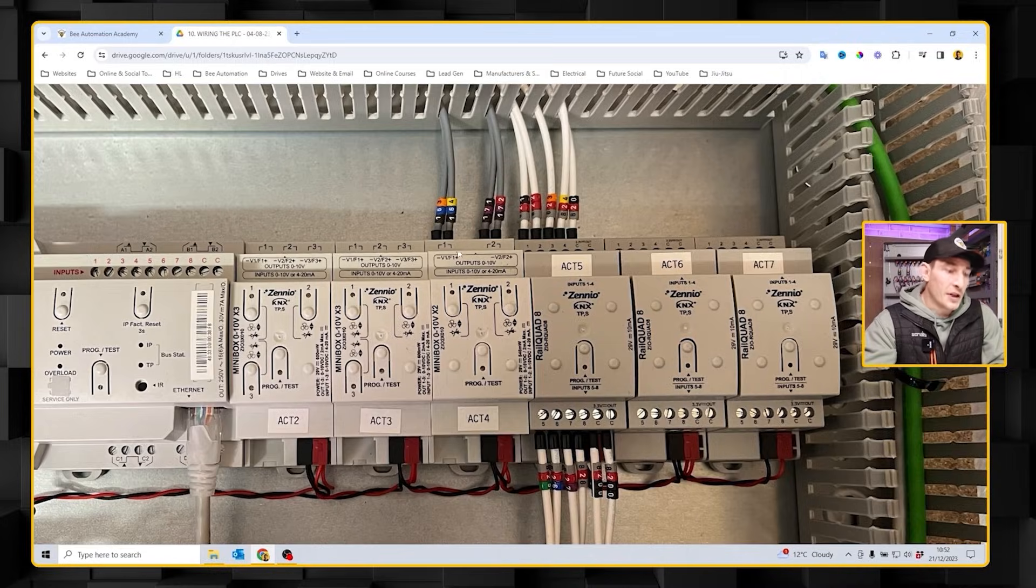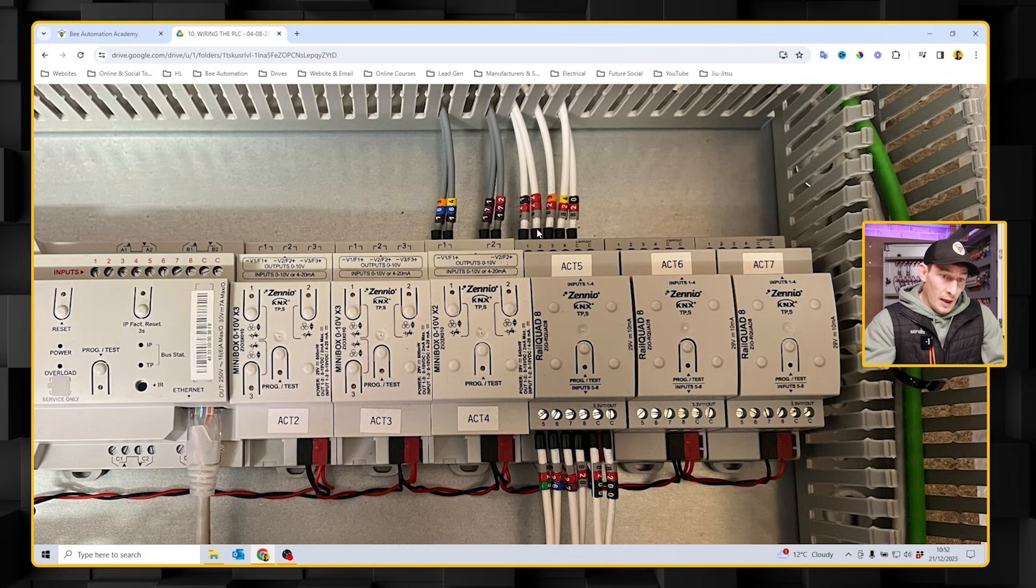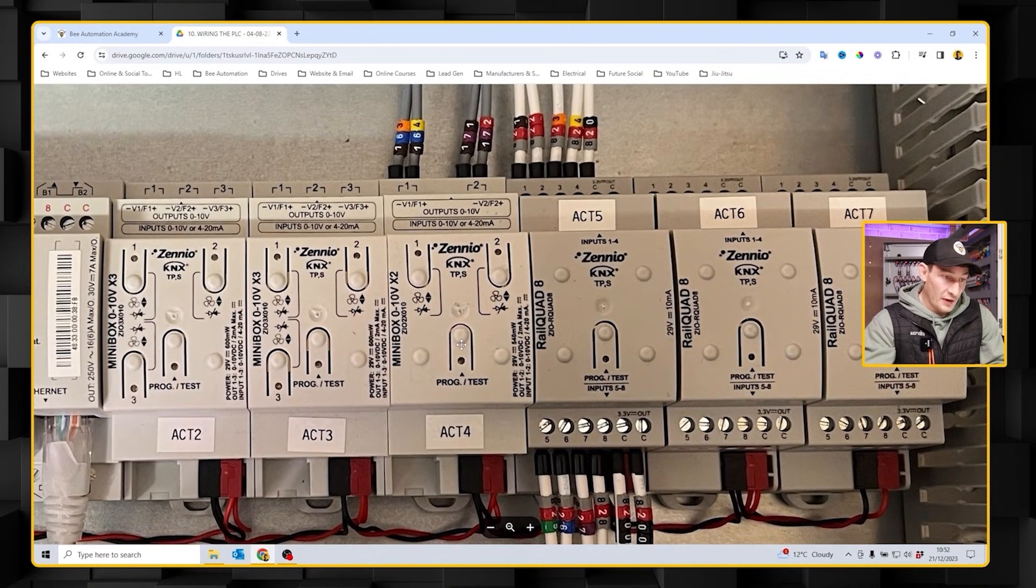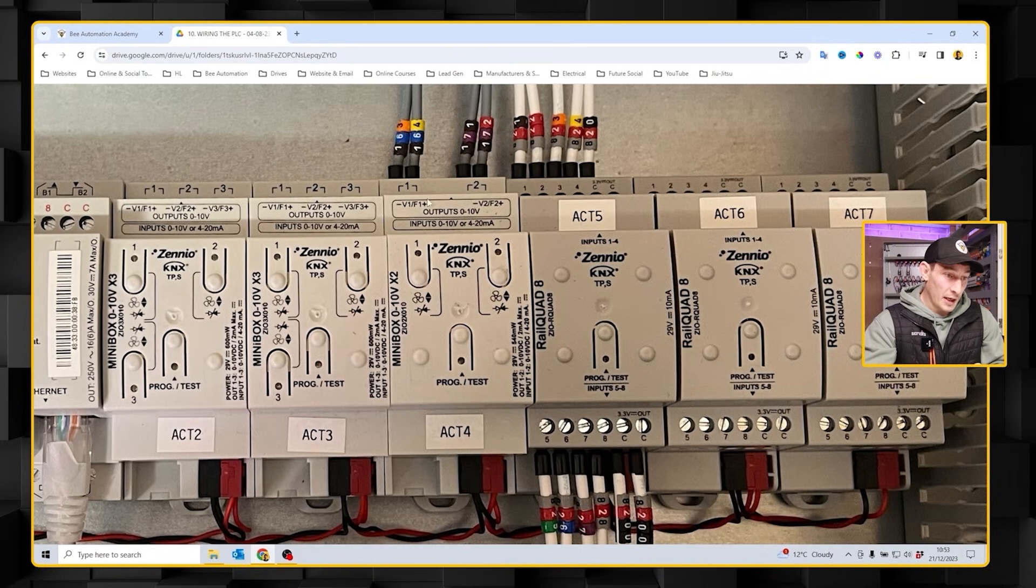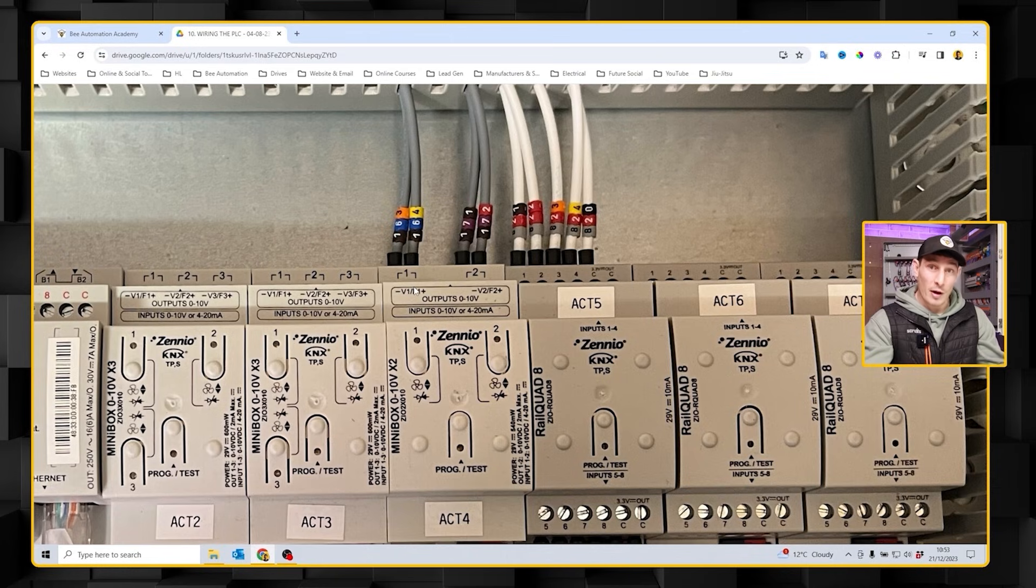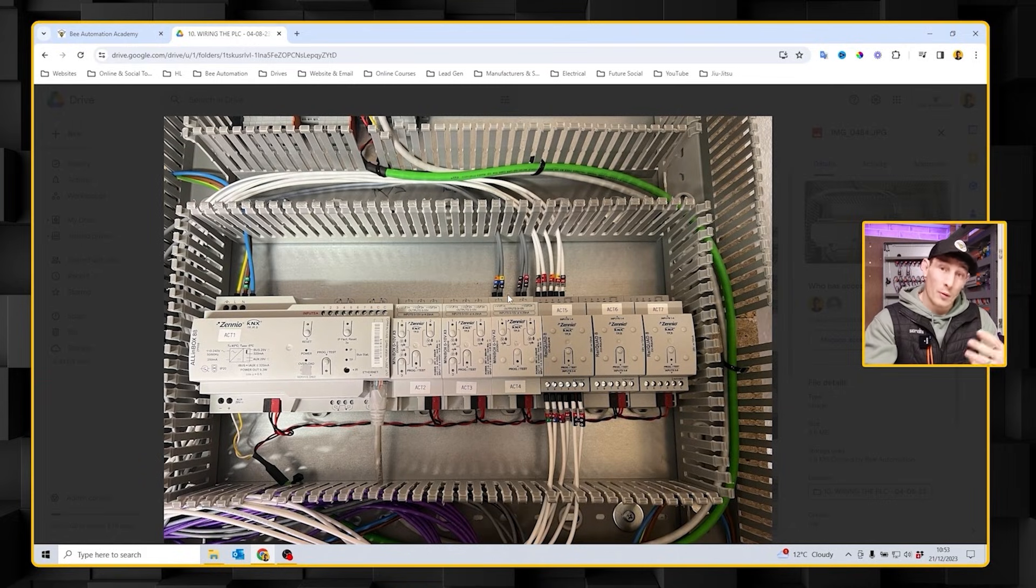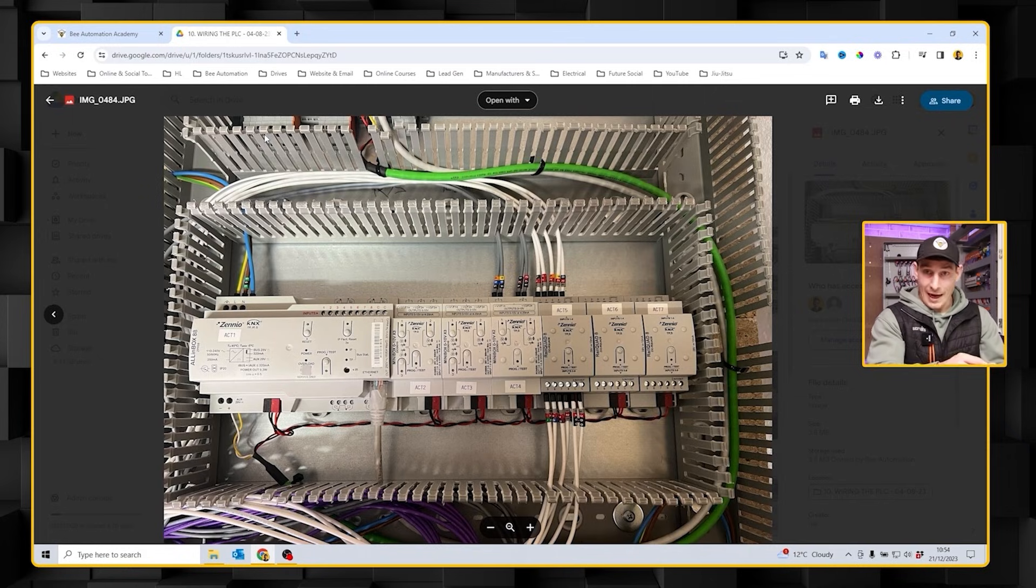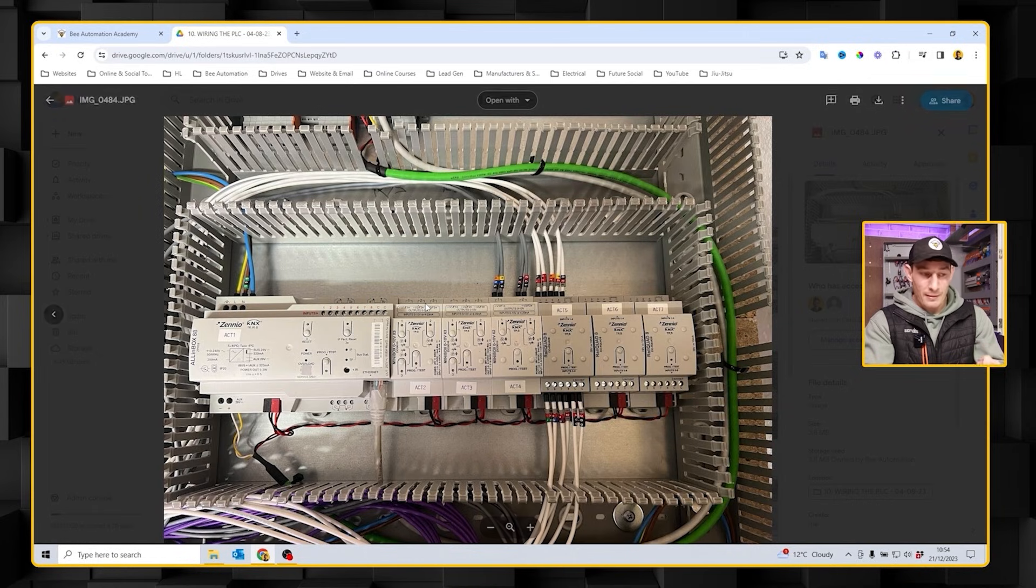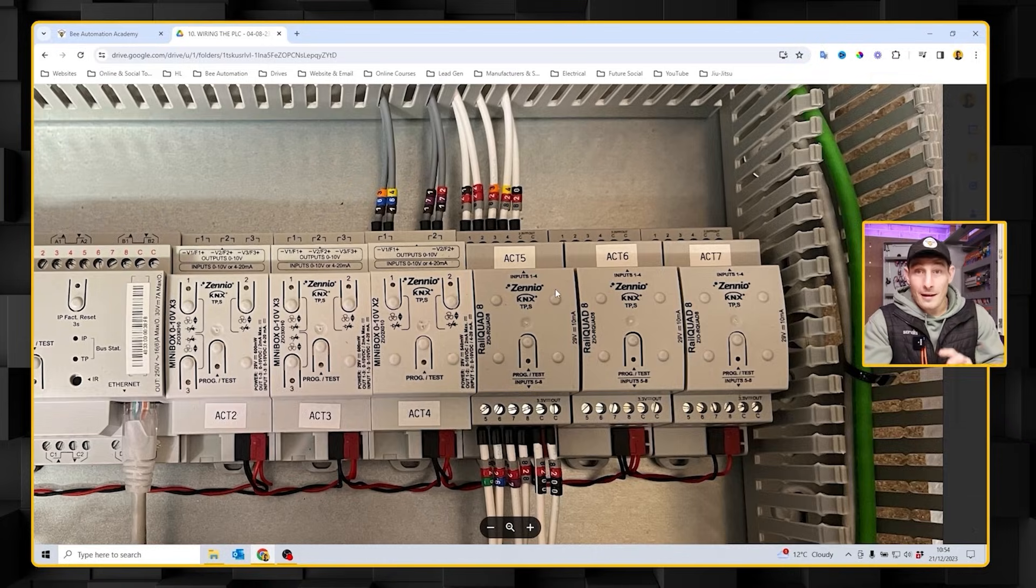We've got a 0 to 10 volt range where 10 volts might be the boiler at 90 degree heat, 1 volt is 30 degree heat, and 5 volts is somewhere in the middle. The wiring for inputs and outputs is very straightforward. As you can see it's just single core cable. This module, actuator 1, has 0 to 10 volt outputs on terminals 1 and 2 for two boilers. What they're ultimately doing is sending out that 0 to 10 volts depending on how we've programmed the system, going off to terminal blocks within the control panel, and then field wiring connects to those terminal blocks carrying that signal to the boilers.